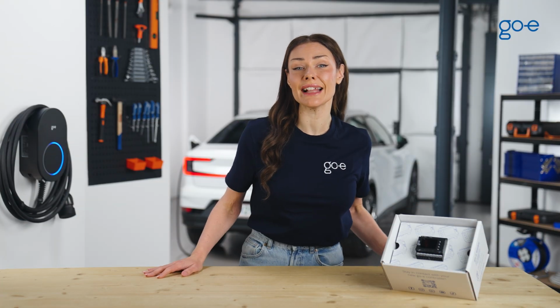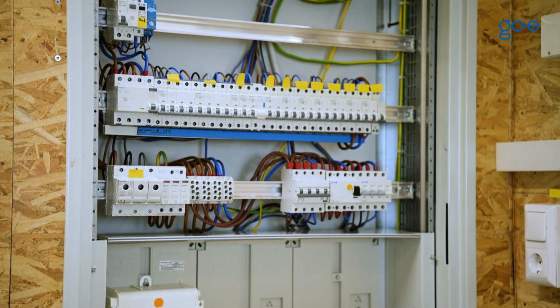For the installation location, we recommend an electrical distribution board that offers space for at least 4 modular units for the go-e Controller and possibly a little extra room for a new circuit breaker. Alternatively, it is also possible to install the go-e Controller in a new surface-mounted or flush-mounted distribution box next to it, and then route the connection cables for voltage measurement and the current transformers to that box.